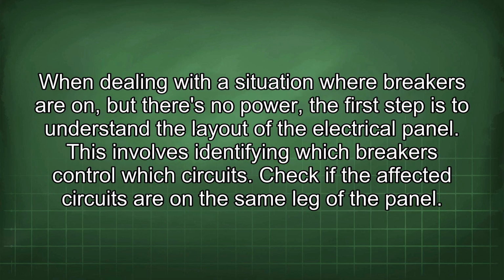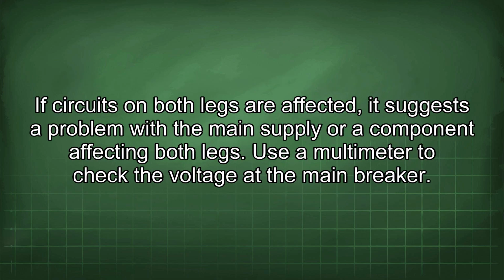When dealing with a situation where breakers are on but there's no power, the first step is to understand the layout of the electrical panel. This involves identifying which breakers control which circuits. Check if the affected circuits are on the same leg of the panel. If circuits on both legs are affected, it suggests a problem with the main supply or a component affecting both legs. Use a multimeter to check the voltage at the main breaker.